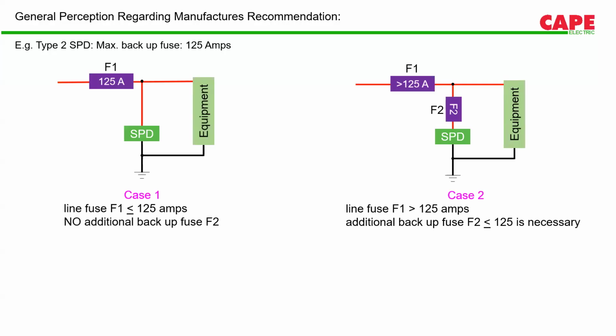So when a manufacturer says that the maximum backup fuse which can be used with their SPD is 125 amps, it means if the incomer rating of the DB where the SPD has been installed is less than 125 amps, that means F1, let's say we call it F1, if F1 is less than 125 amps, no additional backup fuse is required with respect to protection. That is with respect to protection. No backup fuse is required.